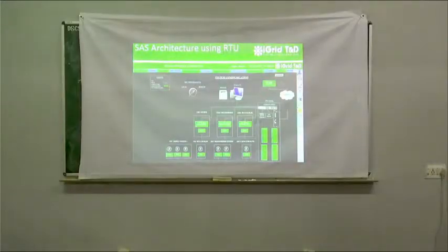Now I will tell you the difference between substation automation using a bay control unit and an RTU. For the new substations, whatever they propose, say for example in Karnataka, up to 132 kV voltage level they use remote terminal units. Above 132 kV, that is 220 kV, 400 kV and so on, they use a BCU type of architecture. So what is the difference between an RTU and a BCU? The RTU is similar to your BCU, but it does not have an HMI.